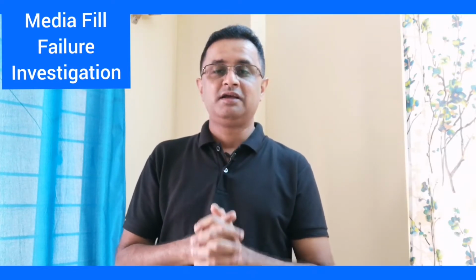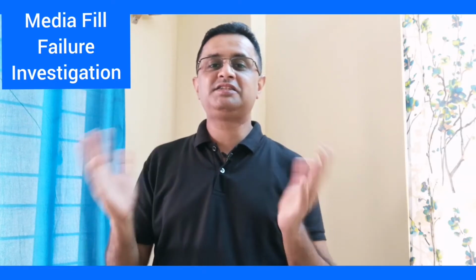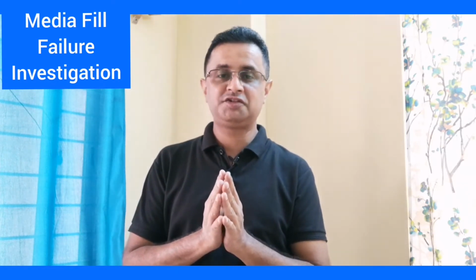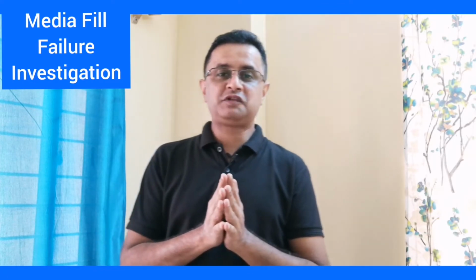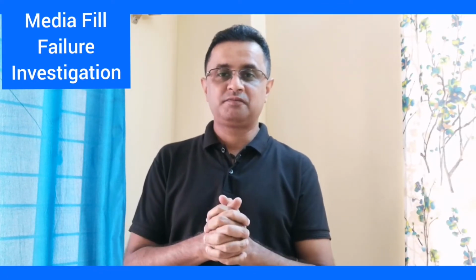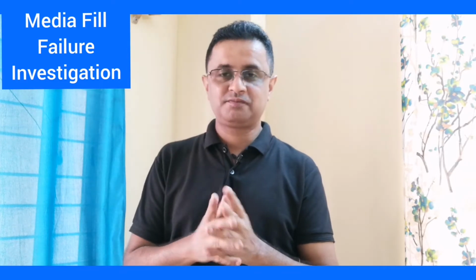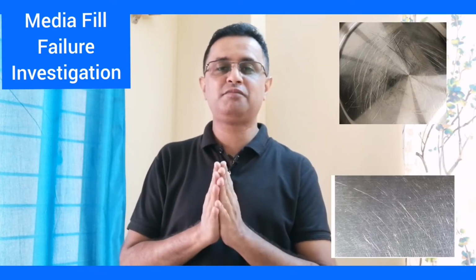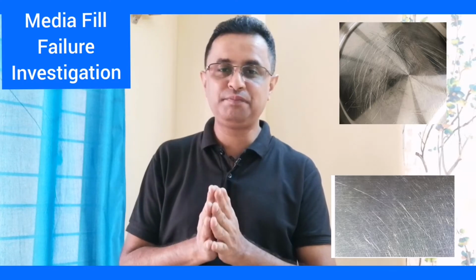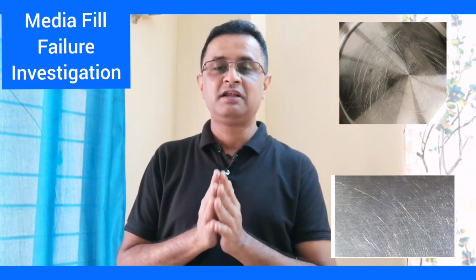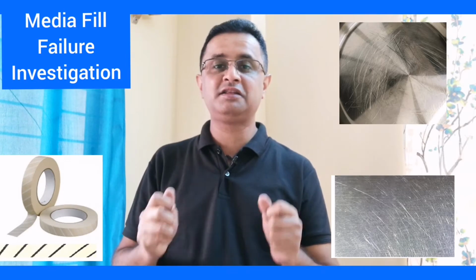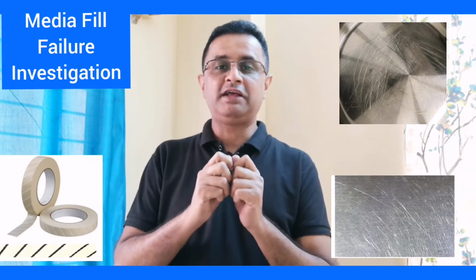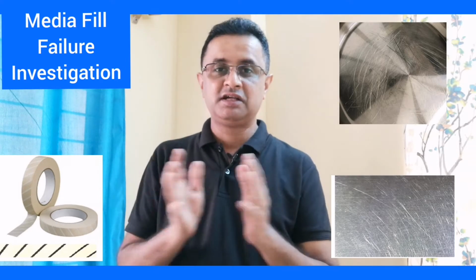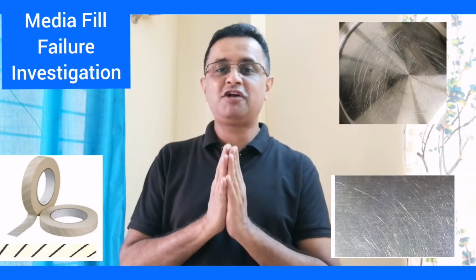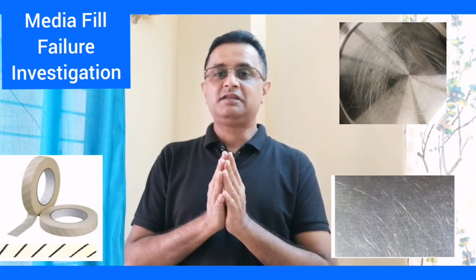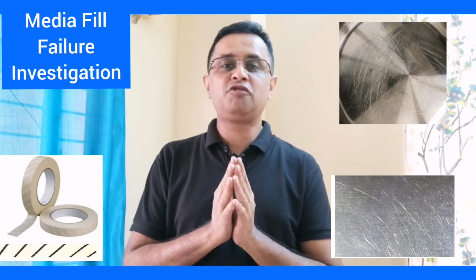Second thing is the inside surface, or inner surface, cleaning of the sterile vessels. Many times you observe that people stick tapes, the autoclave tapes, the sterilization tapes, inside, and that should not be done. But sometimes, due to lack of awareness, for the sterilization validation they use tapes to stick biological indicators or the sensors. And what happens is that these tapes may not be removed completely, and sometimes they are in such a location that they will not be easily visible.